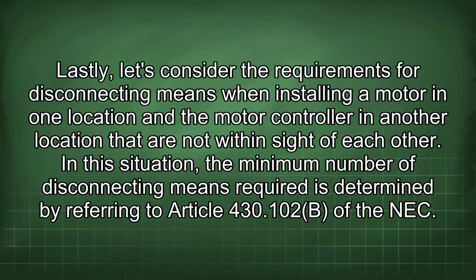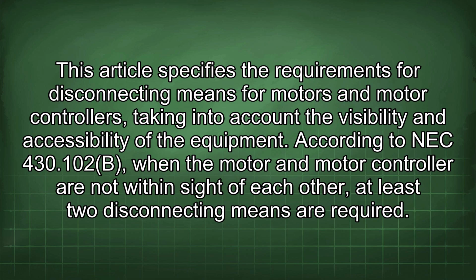Lastly, let's consider the requirements for disconnecting means when installing a motor in one location and the motor controller in another location that are not within sight of each other. In this situation, the minimum number of disconnecting means required is determined by referring to Article 430.102(B) of the NEC. This article specifies the requirements for disconnecting means for motors and motor controllers, taking into account the visibility and accessibility of the equipment.